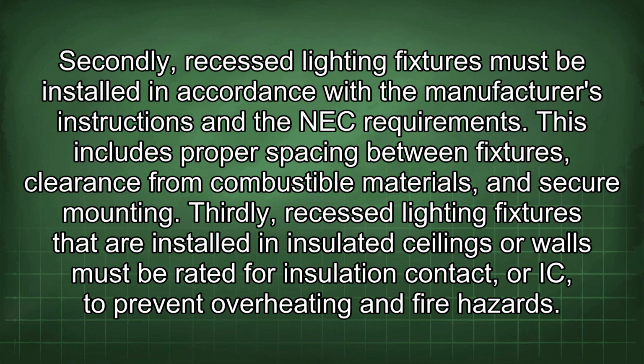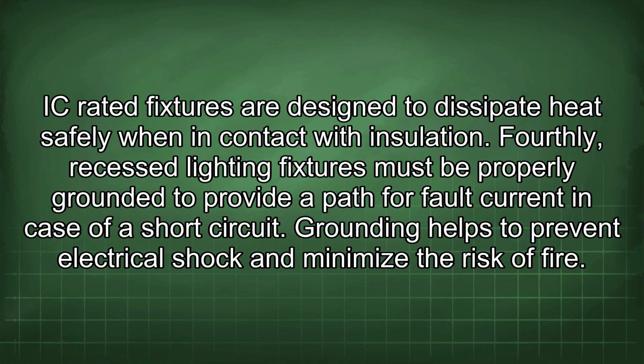Thirdly, recessed lighting fixtures that are installed in insulated ceilings or walls must be rated for insulation contact, or IC, to prevent overheating and fire hazards. IC-rated fixtures are designed to dissipate heat safely when in contact with insulation. Fourthly, recessed lighting fixtures must be properly grounded to provide a path for fault current in case of a short circuit. Grounding helps to prevent electrical shock and minimize the risk of fire.